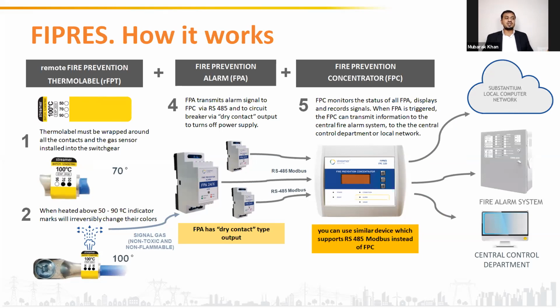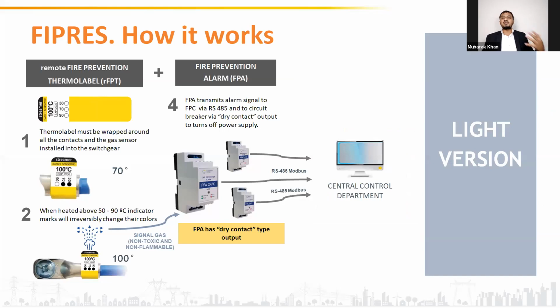At 100 degrees Celsius, the signal gas will be released from the RFPT. It will be detected by the FPA, which is installed in the same cabinet. FPA will communicate the information to FPC, which will display the data, give annunciation, and communicate it to the remote system. There is a lighter version of this FIPRES where we can use the RS-485 directly in your existing control system, and you can eliminate the requirement of the FPC also if you have that facility within yours.